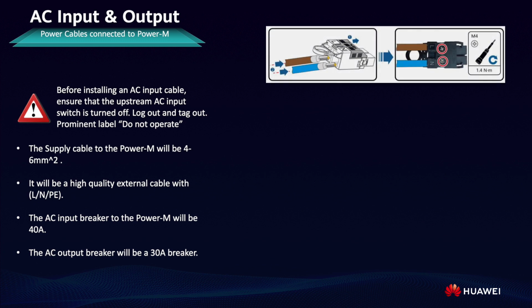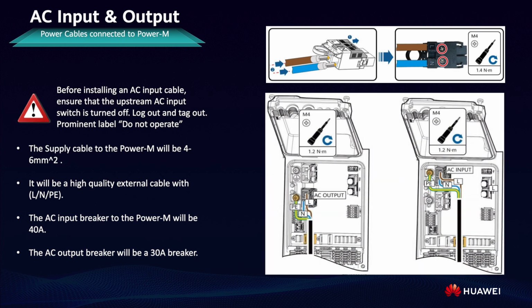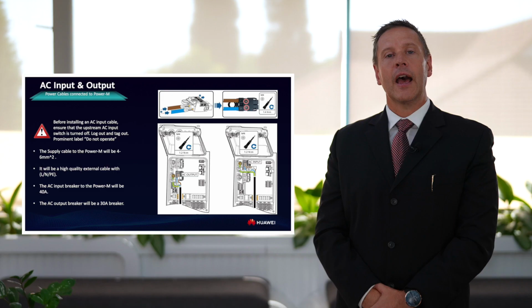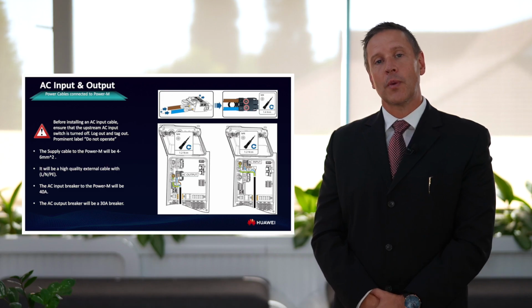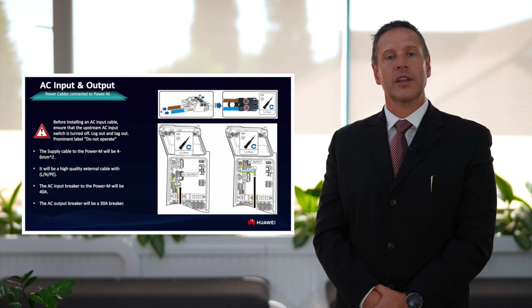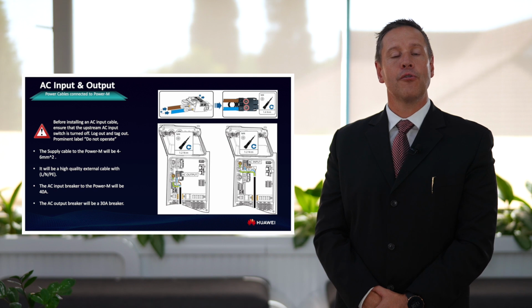The product is supplied with boot-lace ferrule crimps. The boot-lace ferrule crimps will be tightened into the AC connector input and output terminals. You basically slide the cover open, insert the cables and secure it properly. The AC output as well as the input terminal blocks are fast disconnect and connect, and can therefore easily be removed in the event of servicing the unit.